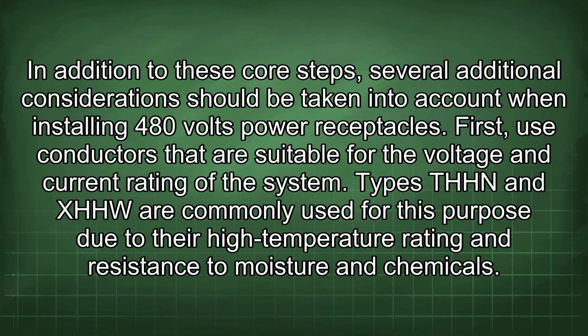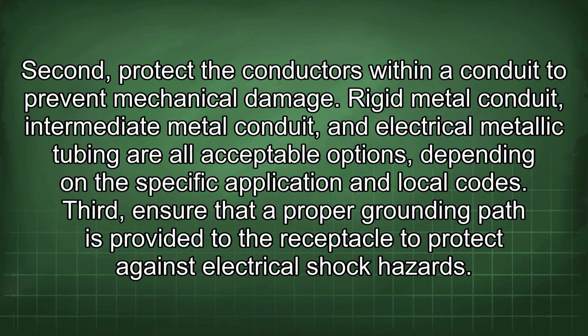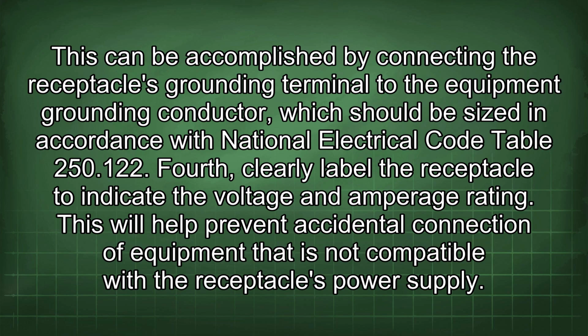Types THHN and XHHW are commonly used for this purpose due to their high temperature rating and resistance to moisture and chemicals. Second, protect the conductors within a conduit to prevent mechanical damage. Rigid metal conduit, intermediate metal conduit, and electrical metallic tubing are all acceptable options depending on the specific application and local codes. Third, ensure that a proper grounding path is provided to the receptacle to protect against electrical shock hazards. This can be accomplished by connecting the receptacle's grounding terminal to the equipment grounding conductor, which should be sized in accordance with National Electrical Code Table 250.122.